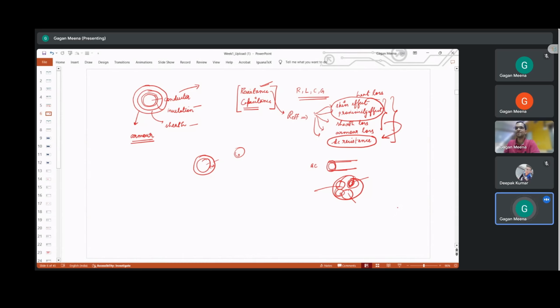Then we move to insulation resistance. Finally, insulation resistance is given by rho divided by 2 pi L, times ln of R over r, where rho is the resistivity, r is the radius of the conductor, and R is the capital R. So T, the thickness of sheath, is capital R minus small r.